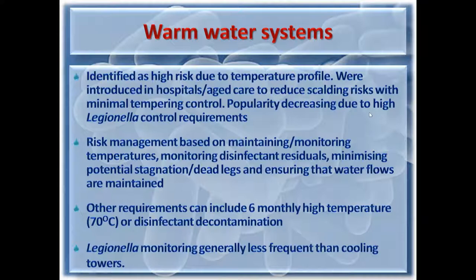Tempering control. So the idea was you'd have the tempering control basically at the inlet to the hot water system. You'd reduce the temperature to 45. The whole system would be operated at 45 degrees. It seemed easier and probably cheaper. But the popularity of those is waning a bit because of high Legionella control requirements. So we're seeing... 60 degrees and then have tempering devices on the individual bathrooms. Risk management for warm water systems is based on maintaining and monitoring temperatures, monitoring disinfectant residuals, minimizing potential stagnation and dead legs, and ensuring that water flows are maintained.